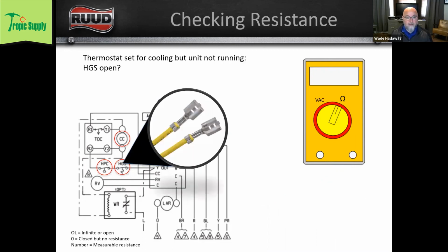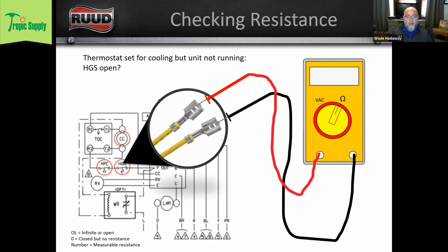that you're testing. So we're going to disconnect the leads from our hot gas switch, and we're going to put our leads from our meter right there to each one of those connectors. You want to make sure when you're doing this that you don't hold the connector and the lead with your fingers, because you can complete a circuit or show resistance across your body as you're testing those, right? So if you've got your red lead in your terminal here and your black lead in your terminal here, you can get a false reading. So you want to make sure you're not putting your fingers or your hands on your connector. Everything's de-energized. You're disconnecting these, and you're going to check across the switch.